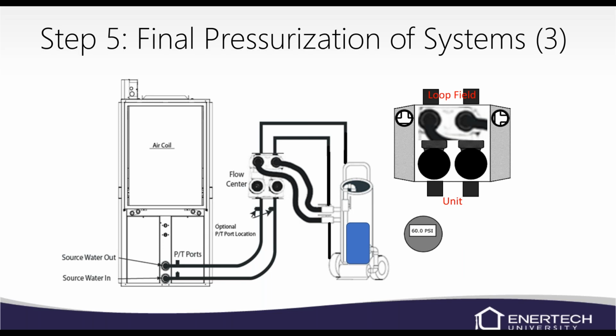Again, pressurized up to about 60 PSI. If ever you need to pressurize a system without a flush cart, if you're out there servicing the equipment, you can use a loop goosing tool, and city water pressure will be, I know around here in Greenville, we have close to 60, if not more, water pressure. But really, as long as we have positive pressure leaving the unit, it's enough pressure in the loop field. We just don't want it to be in a negative pressure when it leaves the unit.